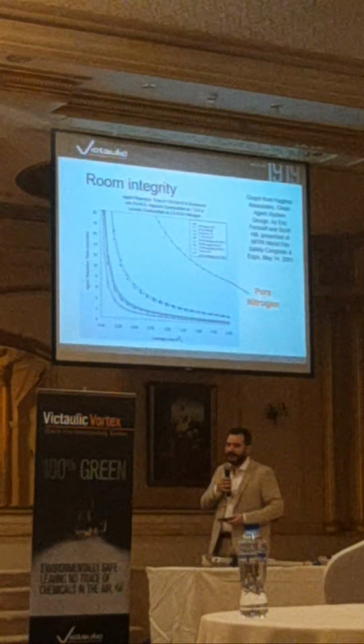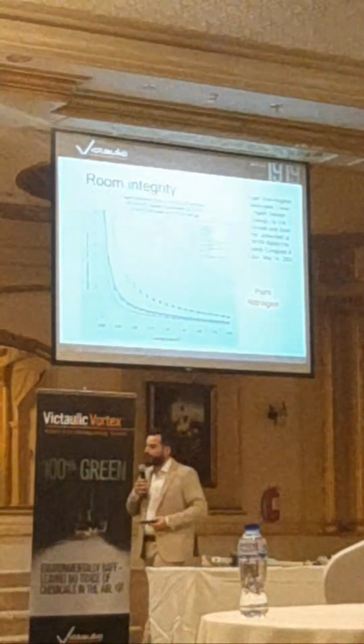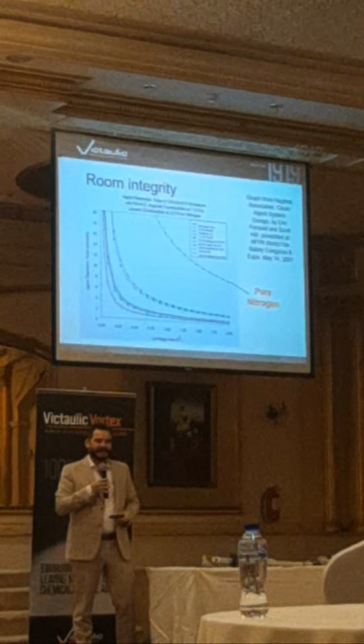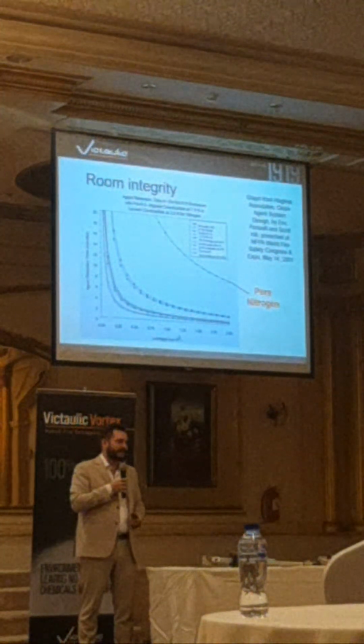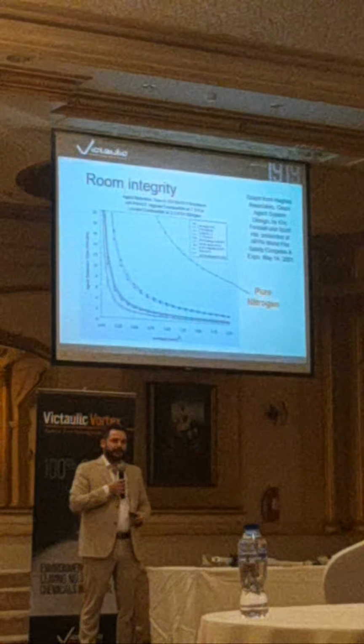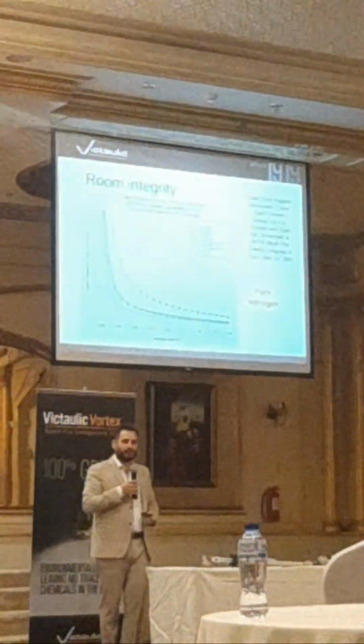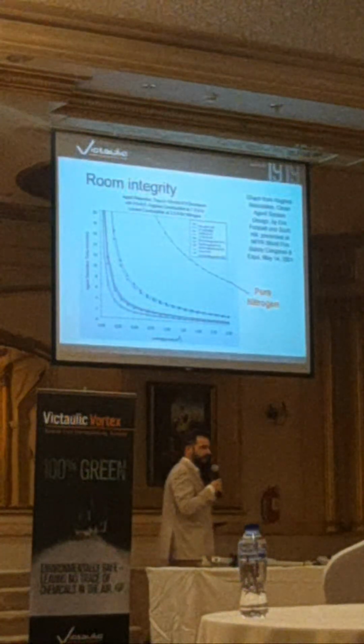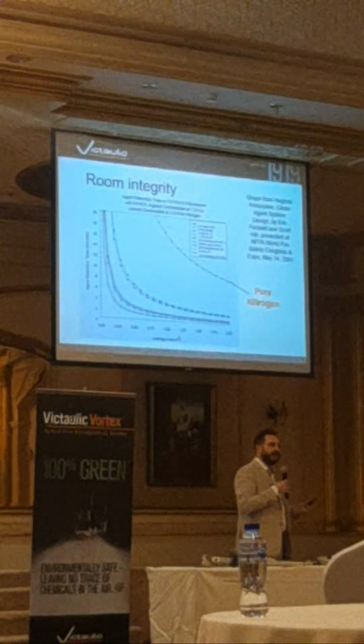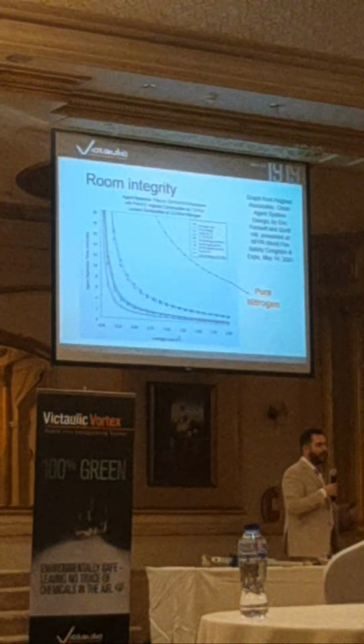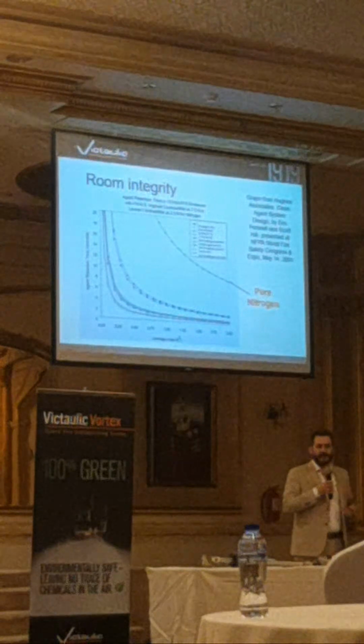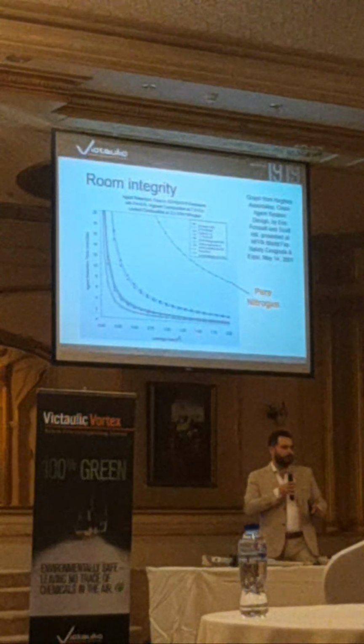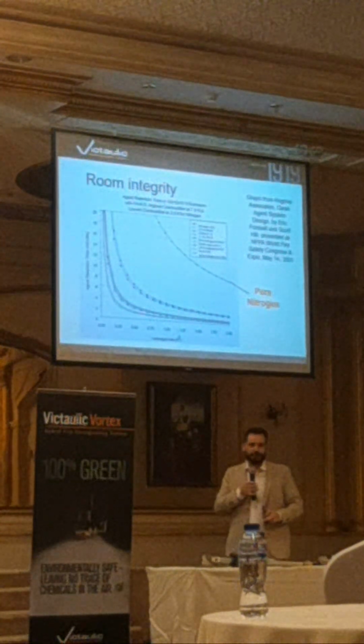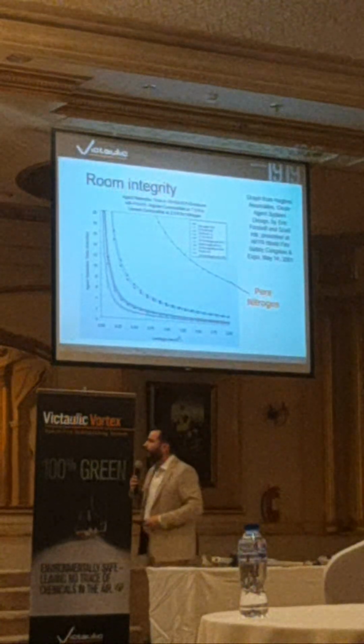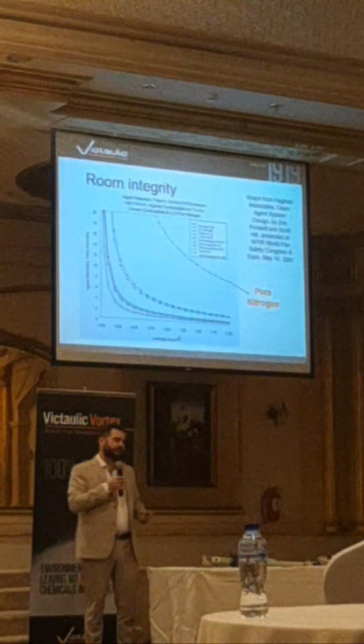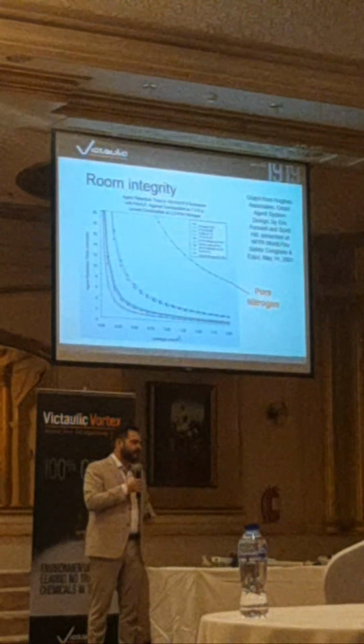What we're seeing here is that the NFPA did testing on different gases. You can see it's an old slide because the first gas used is halon, which is no longer used globally for environmental reasons. There's also nitrogen, FM200, CO2 — just a comparison of different gases. I believe Novec wasn't really invented yet, or not really in the market at that time, but you can compare it similarly to FM200 on the graph.